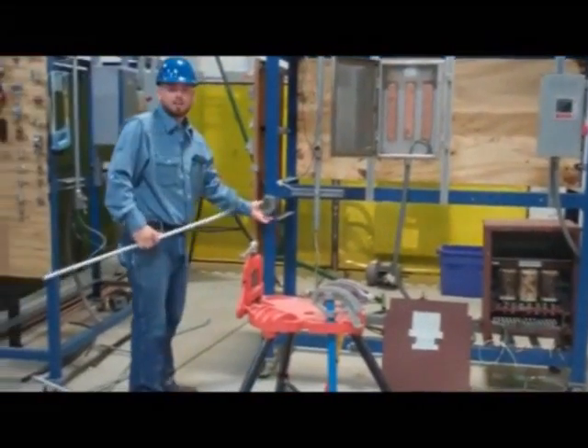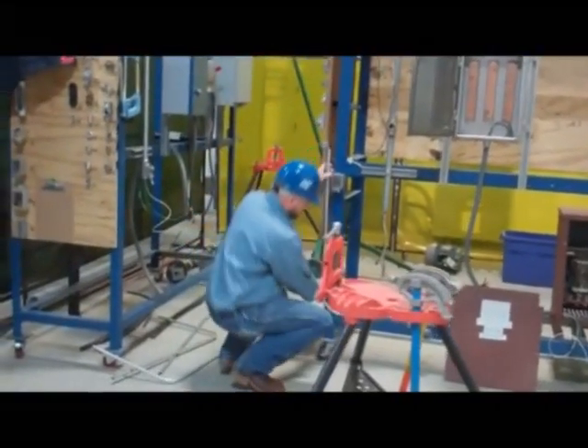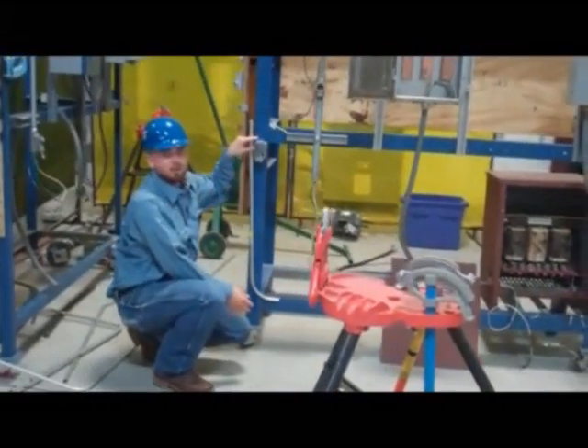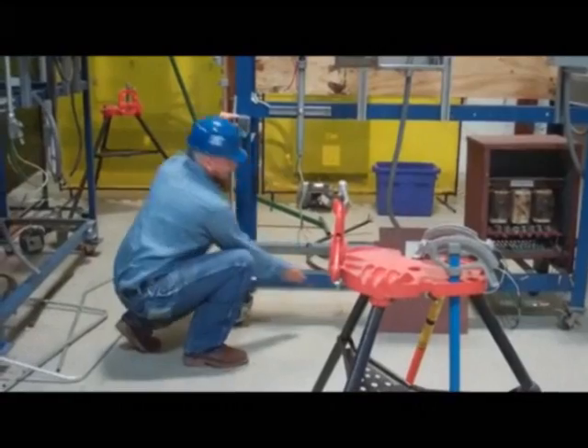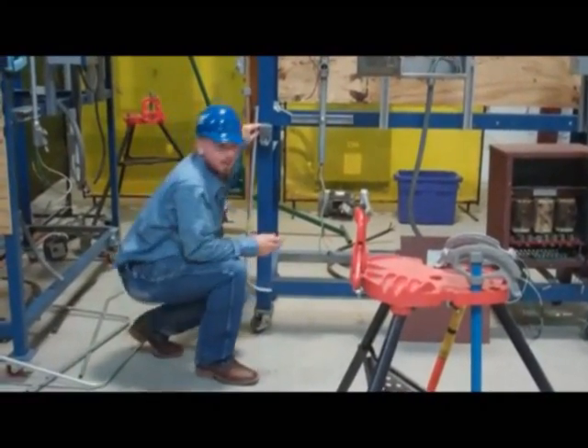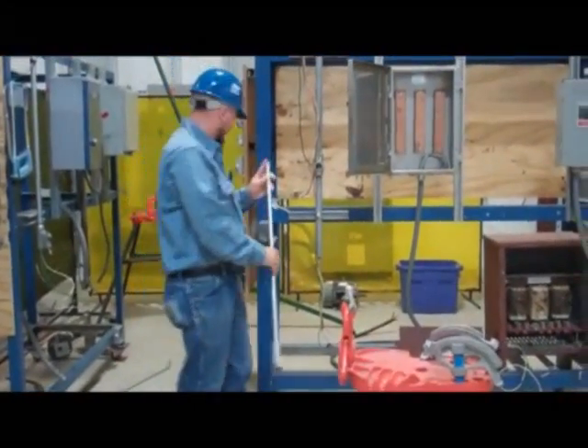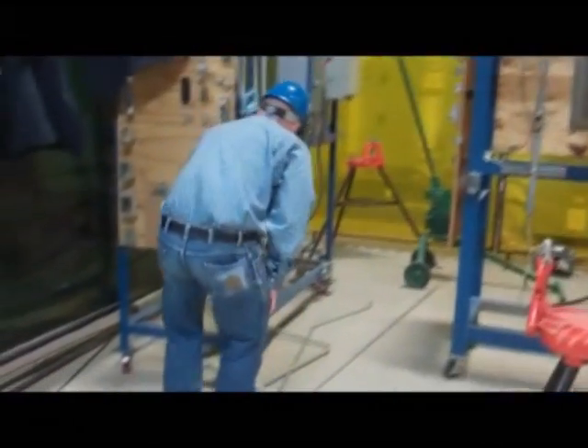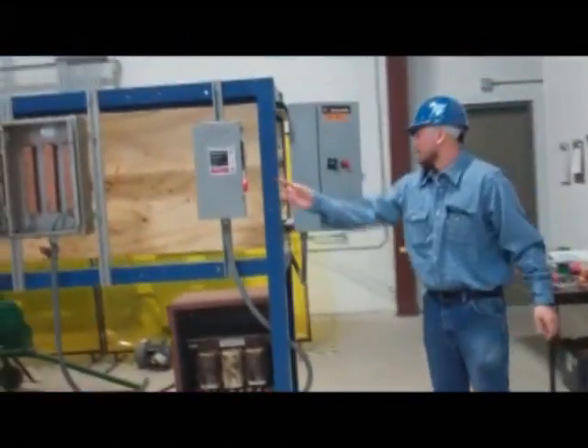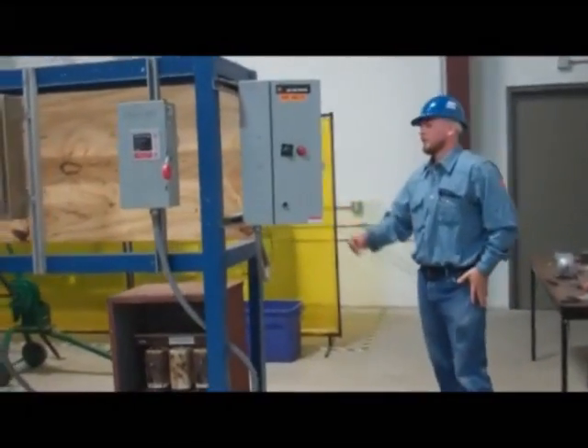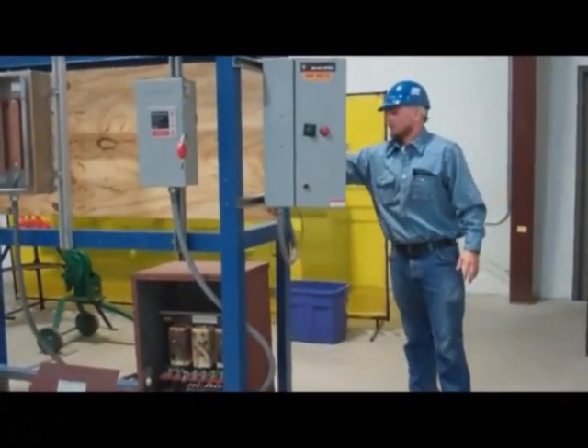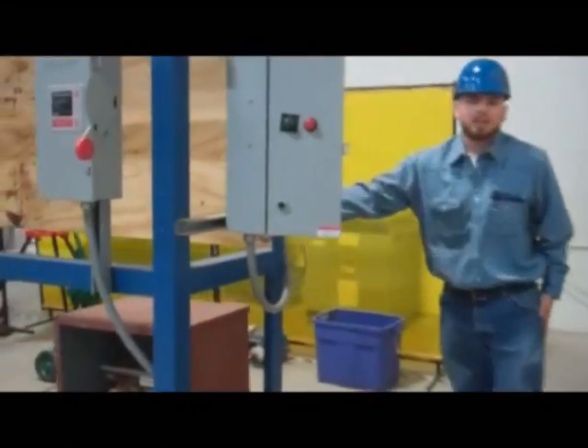As I will say, this box. You get a solid piece of conduit. There's 90 degree. Making nipple, you make the boxes together so you can pull your wire in there and wire up whatever it is that you need. And then once you pull your wiring, whatever you're going to, either a transformer, a disconnect. We also got a start-stop button over here. Most time you see the start-stop buttons a lot in the industrial field for motors.